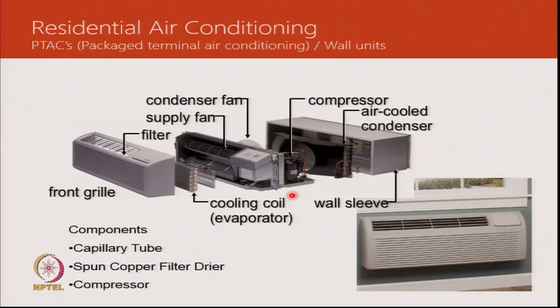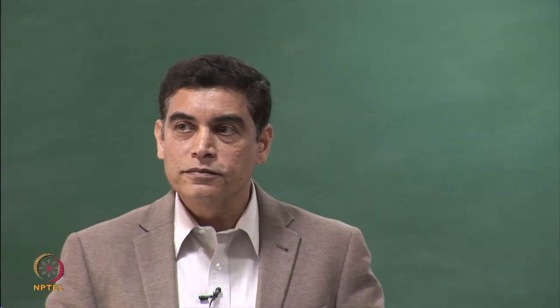Now, if we look at this coil, this will typically go into a residential duct-free split of this nature, and you can see the complexity. From evaporator design, we would also need to look at several other components, and the key component there would be the supply air fan. So that is a tangential blower which consumes in the region of 20 watts of power.